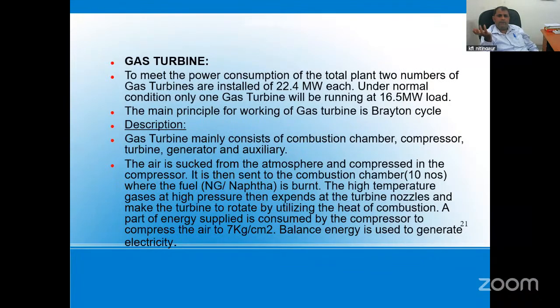But you know that when turbines get older, they do not give 100% efficiency. Out of these two, only one gas turbine is running and the other is standby. One gas turbine develops the power sufficiently to catch up with our client load. We are generating the power through the gas turbine, and natural gas is used as its fuel. All of you know the working principle of the gas turbine. The gas turbine works on the Brayton cycle.